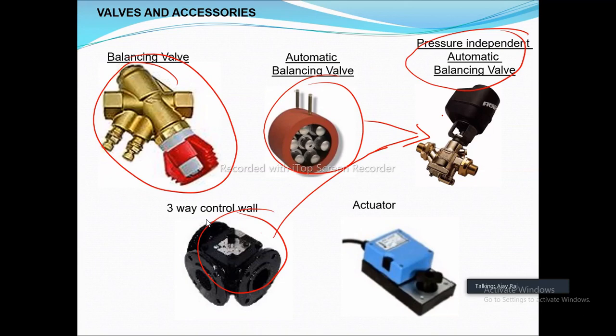So the PICV valve is one step ahead of your control valve. So it can do both the functions. It can control the maximum flow as well as modulate as per the signal from your thermostat. I hope it is clear.